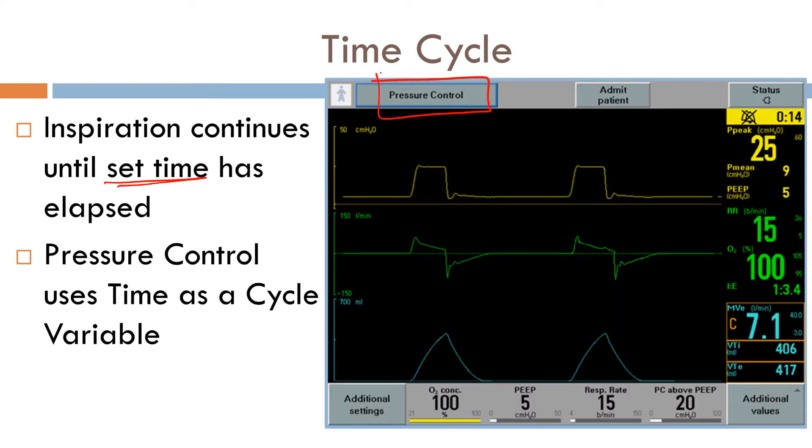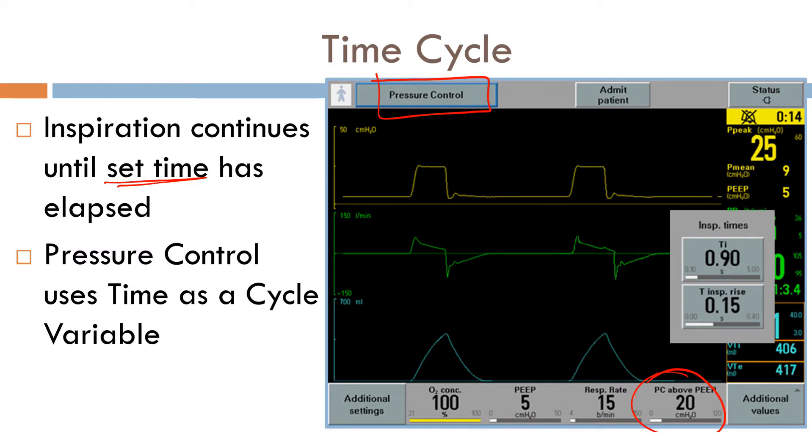We'll talk about what that means in a minute, but let's go over time cycle. The definition is inspiration will continue until a set time has elapsed. So interestingly enough, in pressure control ventilation, the cycle variable is time. As we can see, we're in pressure control. So just to recap, what is our target variable in pressure control ventilation? It's pressure. Now the cycle variable in pressure control is time. I had alluded to this before.